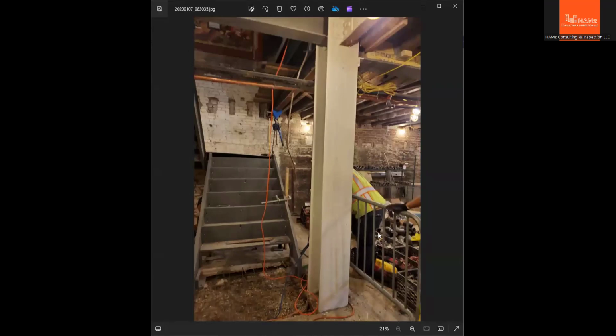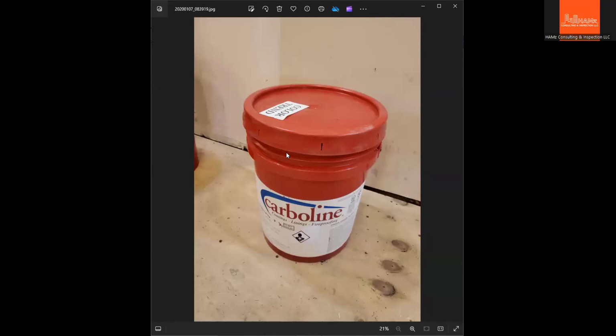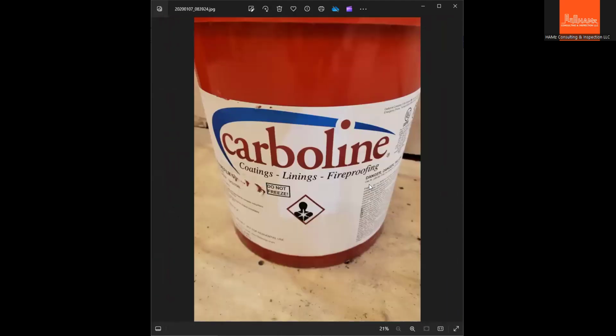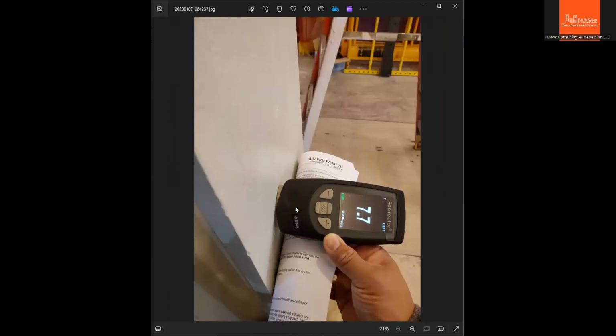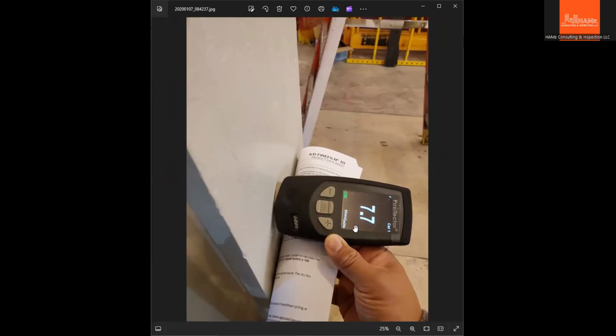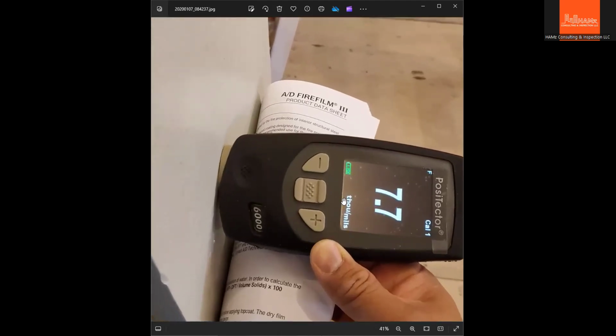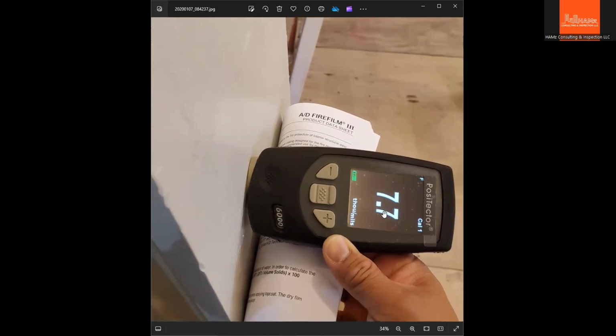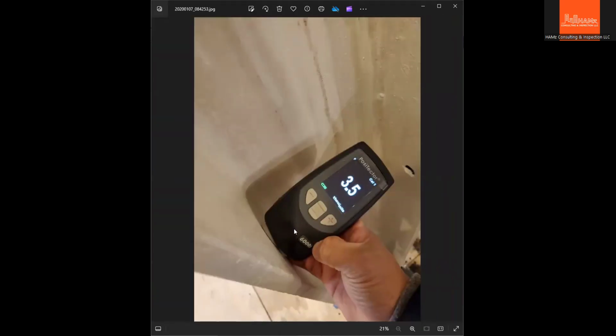So this is on the cellar level. And the material that has been used was identified as Carboline fireproofing coatings. And this is the equipment I use for thickness measurement. As you can see, this is 7.7 mils, or thousandths of an inch, mils. It's 7.7 mils. Currently, that's the thickness that has been measured. So that's the inner side surface of the flange. This is the web.